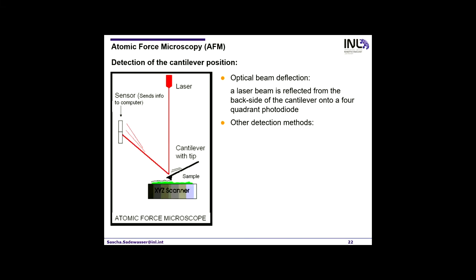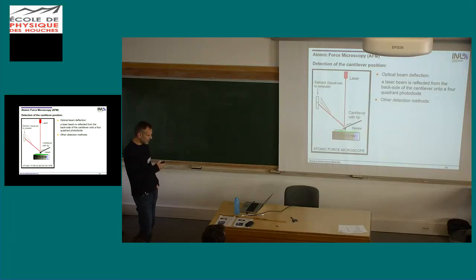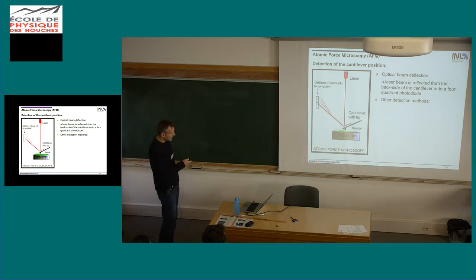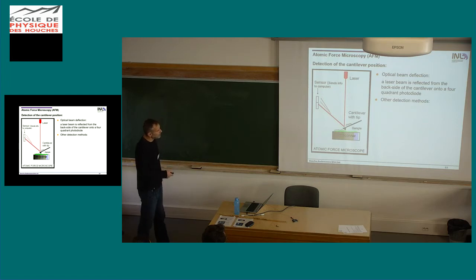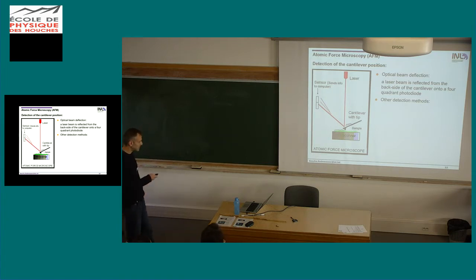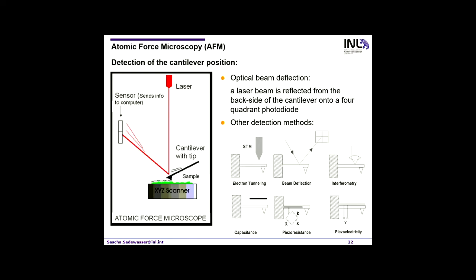And instead of using an STM on the backside of the cantilever, nowadays what's most common is to use a laser. So you shine a laser onto the backside of the cantilever, which is reflected to a position-sensitive photodiode. So these are four small photodiodes, a four-quadrant photodiode, to measure how the beam is deflected on the backside. And of course, you know this very well, a small movement here makes a big movement over there, so you're very sensitive to small movements of the tip with this. But there are also other detection modes. We saw this one already. This is the beam deflection.